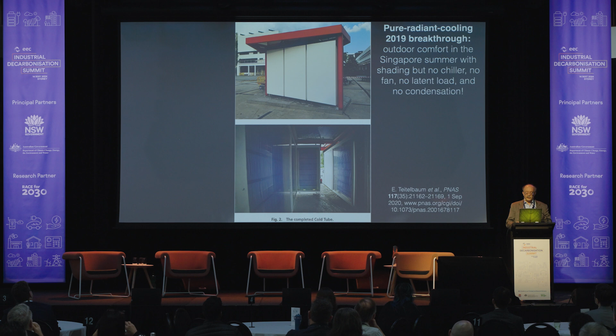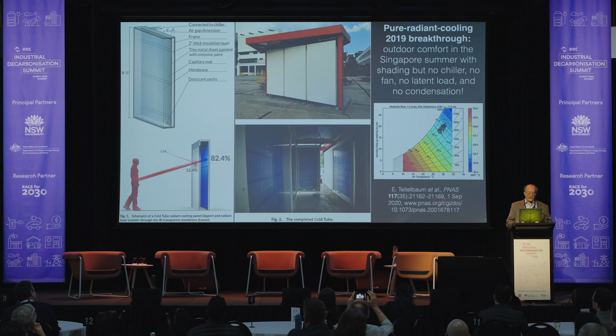But an experiment 5 years ago revealed a startling alternative. Purely radiative cooling kept people comfortable outdoors in Singapore without moving, drying, or cooling the air. Instead, in a shaded but open-ended pavilion of about 10 square meters, people stayed cool just by radiating their bodies' far-infrared rays into panels circulating slightly cooled water, shielded from the humid air by an air-gap plastic film. Radiant temperatures of 23 to 25 degrees could deliver comfort in air up to at least 32 degrees at 80% relative humidity. Such mild cooling, just 7 to 9 degrees below ambient, can often be done passively with no electricity, potentially eliminating the world's long-term growth in peak electricity demand.